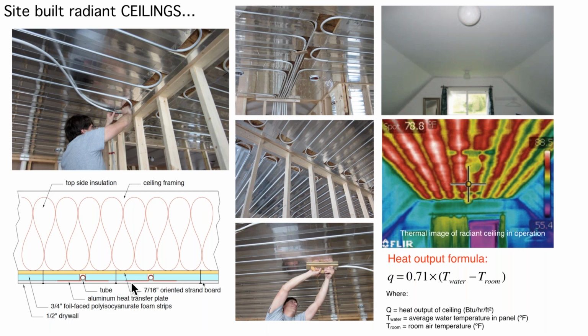And of course, when the drywall goes up, you don't want to shoot the screws up into the tubing. So typically, you're going to snap some lines and shoot the screws in halfway between the different rows of tubing. 2.5-inch screws work really good, and then just finish it off. So here's a ceiling in a room. This is with an attic truss.